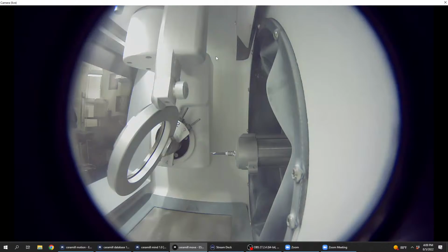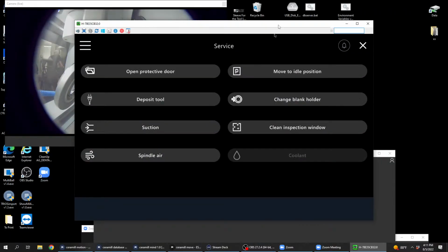If I go to HMI remote control, we can basically look together at what is on the HMI display. I can pause the tool, open the door, turn on the suction air, whatever, and change the blank holder. I'll go to the menu and go to maintenance, say calibrate machine, and then you can see the on-screen instructions now.